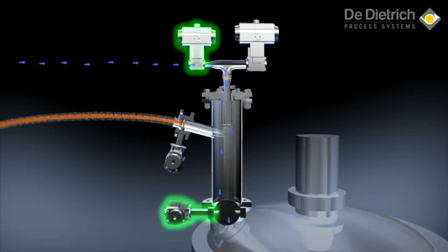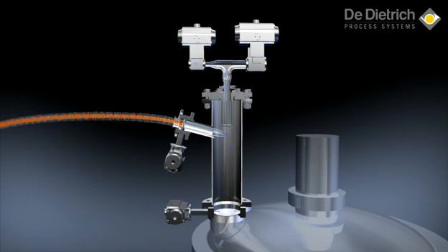The nitrogen valve remains open to help prevent oxygenated or solvent-laden air from entering the powder pump body. Following discharge, the powder outlet valve closes, then the nitrogen isolation valve closes.